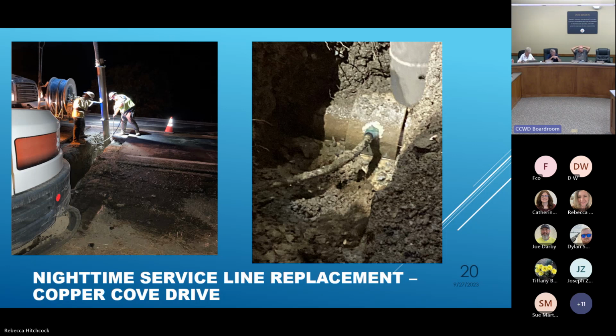Yep. So what you're looking at here is threaded right into the coupling of the two AC mains, just a direct threaded connection. We're able to unthread that. Oftentimes what fails, and what happens on some of the services in Rancho, is those threads fail, which makes it a difficult work effort. We may have to cut out the coupling, connect to both sides of the main, and then put in a tap.